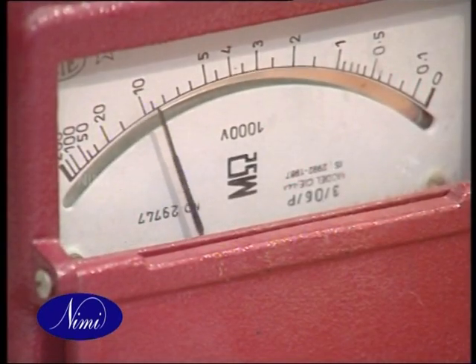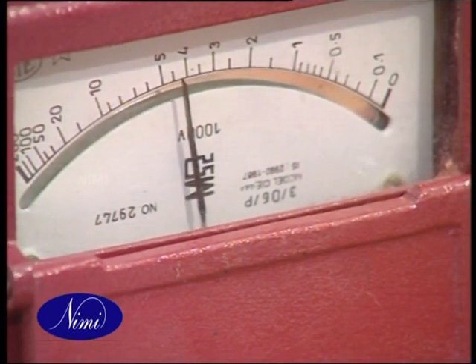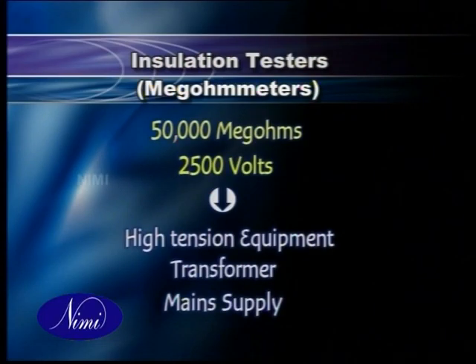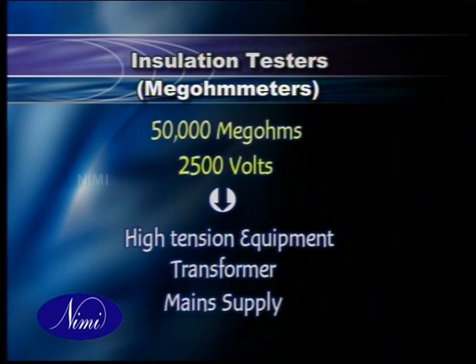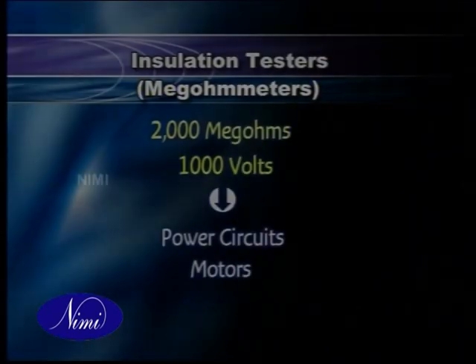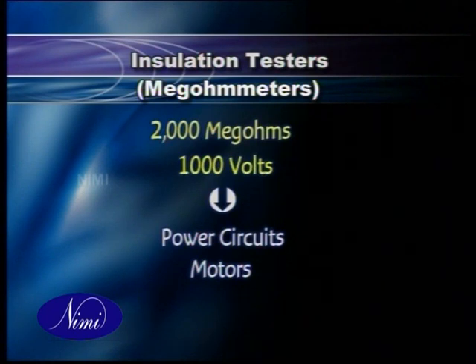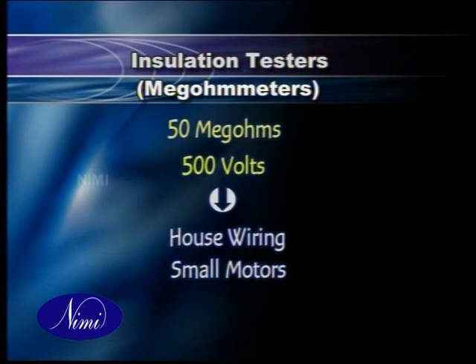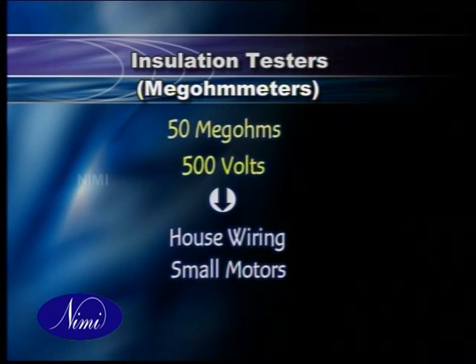However, it is recommended to rotate the handle at the rated speed to obtain a steady voltage. As megas are designed to measure very high values of resistance, they are used for insulation tests. A 50,000 megohms, 2,500 volts mega is to be used to test high tension equipment, transformers, main supply, etc. For testing power circuits and motors operating on voltages not exceeding 500 volts, a 2,000 megohms, 1,000 volts mega is to be used. For testing house wiring and small motors operating on voltages not exceeding 250 volts, megas of 50 megohms, 500 volts can be used.